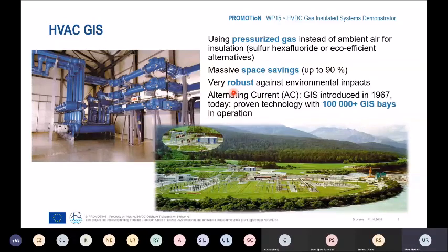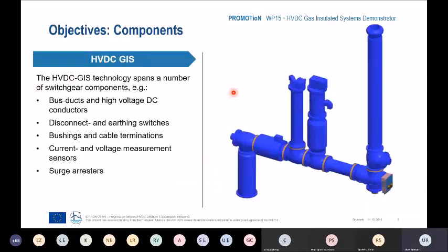Typically, we are using SF6 up to today for gas insulated switchgear, but we are also looking at eco-friendly alternative solutions to reduce the SF6 content in switchgear. A DC switchgear is a little bit different from the AC version. There is no circuit breaker. If you remember the presentation from René, it's not so easy to use the gas insulated version for a breaker. So we are focusing on all other components.